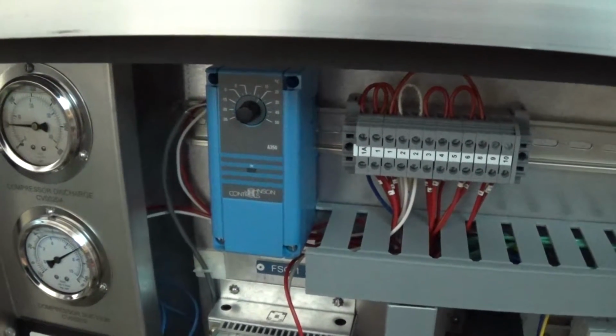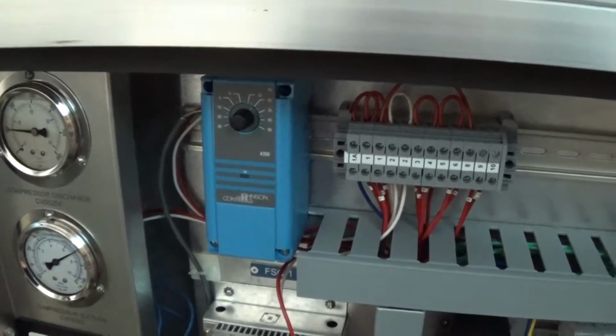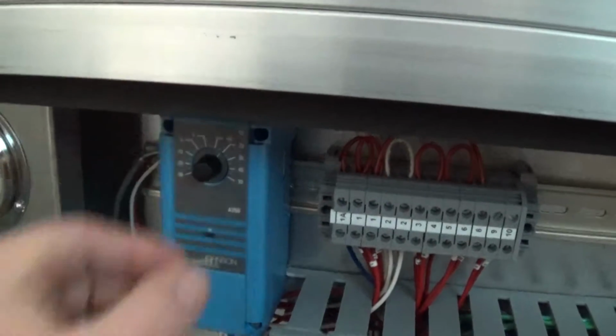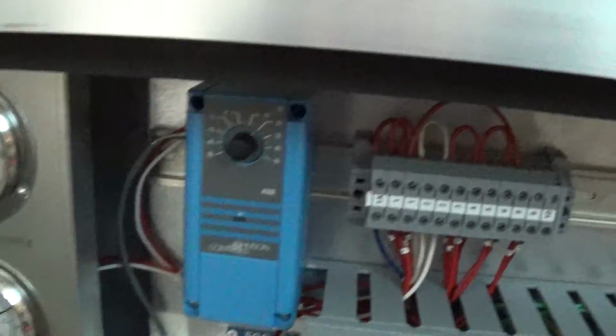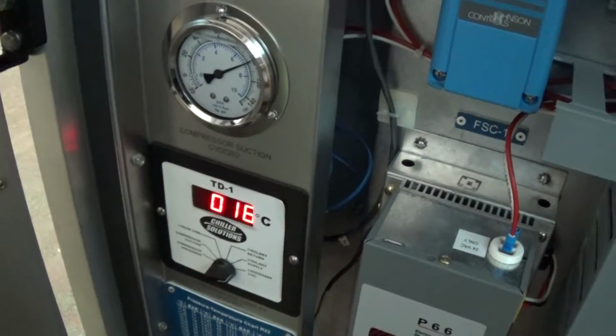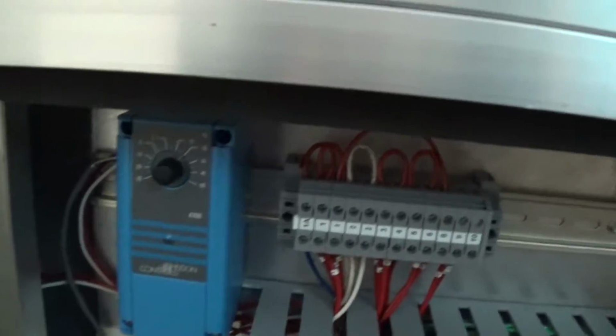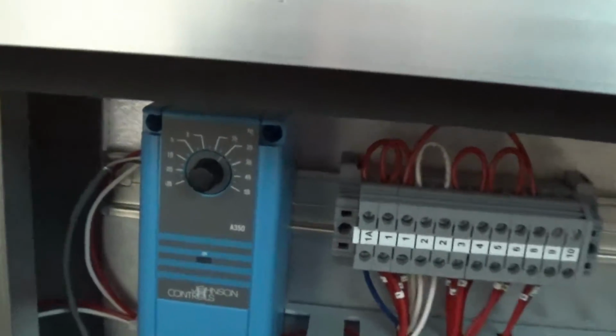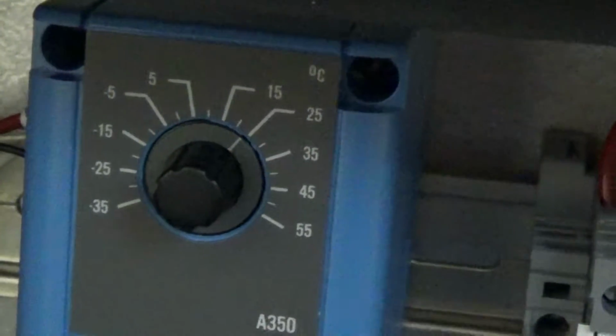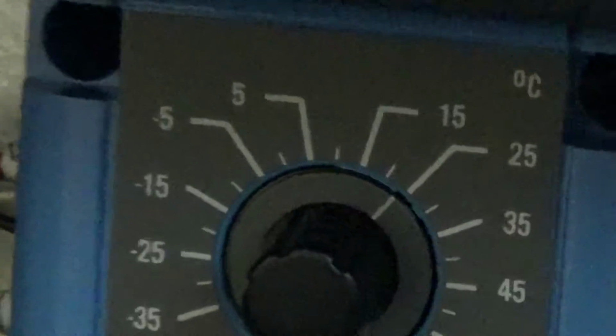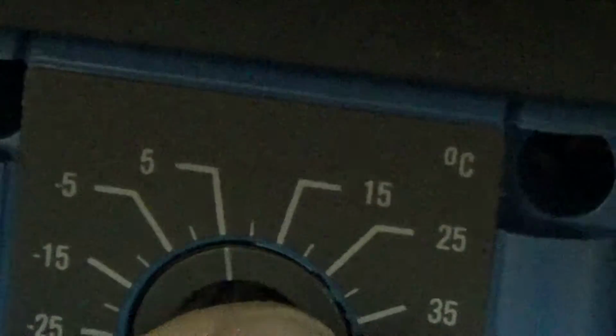In this case here, the thermostat, which controls the temperature on the unit, is a Johnson Controls, just with a rotary dial right here. Right now we have it set up at approximately 25 C, just so we can heat up the tank right now, but right now it's showing the temperature at 16 centigrade. It is fairly sensitive, but we want to bring it down right about to that -2 centigrade mark. You can see there you have -5 and 5, and we want to bring it down just right to about there.